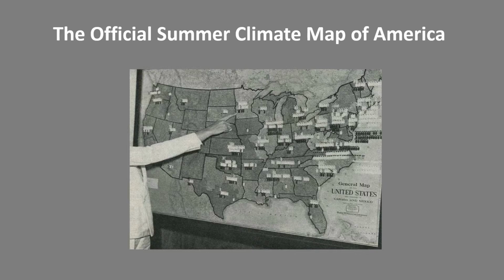This is the official summer climate map of America. You know, down in the southeast, if you're flying down to Baton Rouge in the summertime, you probably walked off the airplane and immediately started sweating and could not wait till you hit your air-conditioned hotel room. It's really hot and it's really humid, and that humidity is the reason we call it air conditioning and not air cooling. Down in muggy places of our country, it is just as important to dehumidify the air as it is to cool. Air conditioners down in this part of the country have to be sized for both latent load, which is the ability to remove moisture from the airstream, and sensible load, which is the ability to cool the air down.